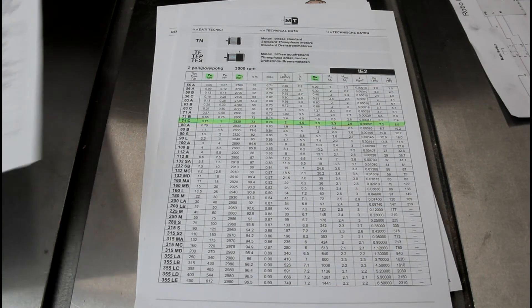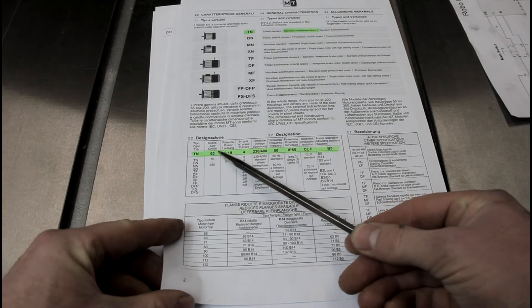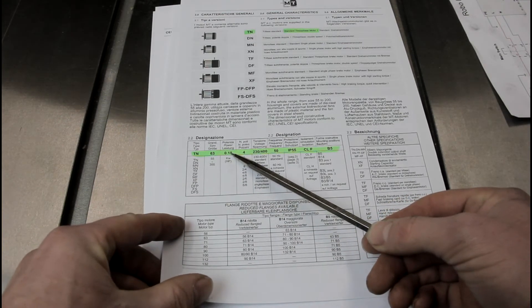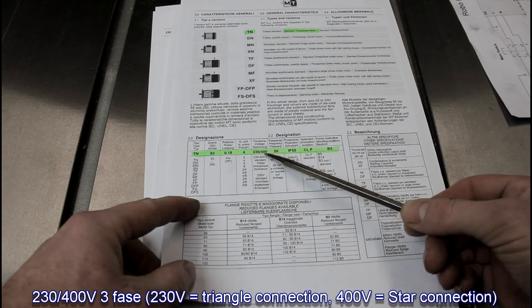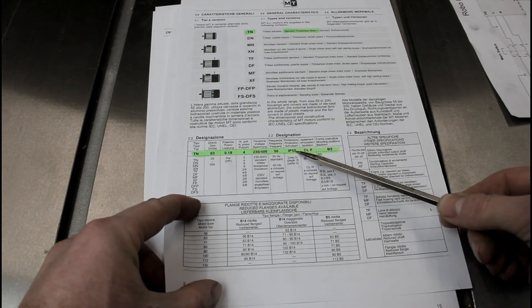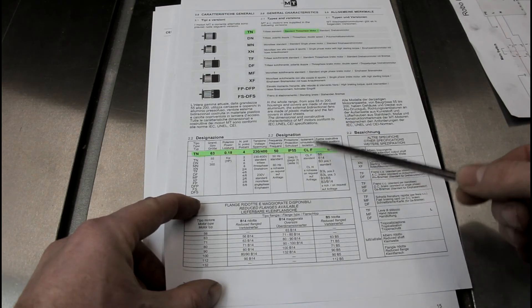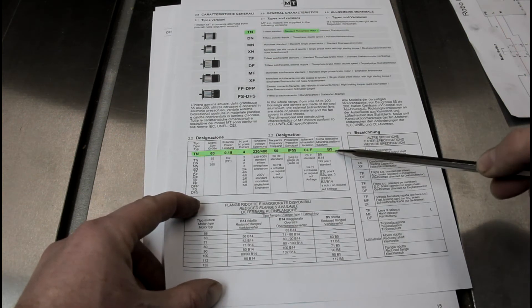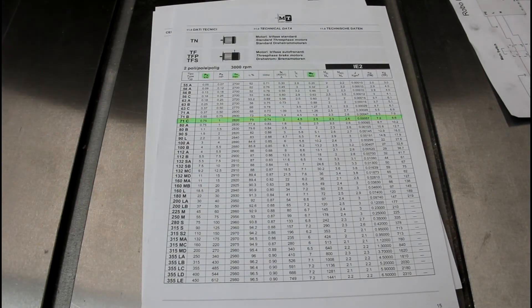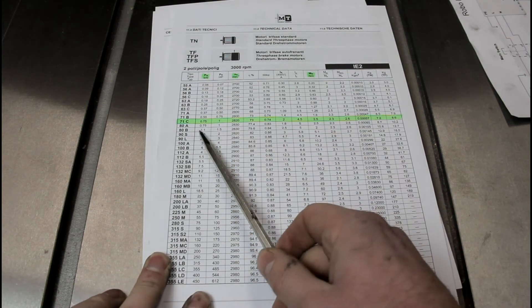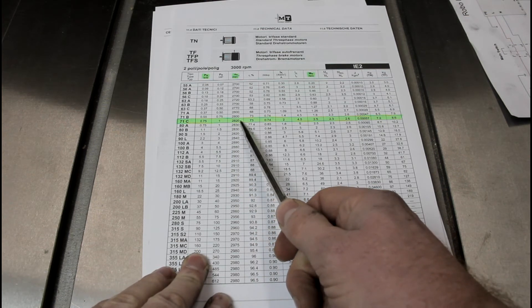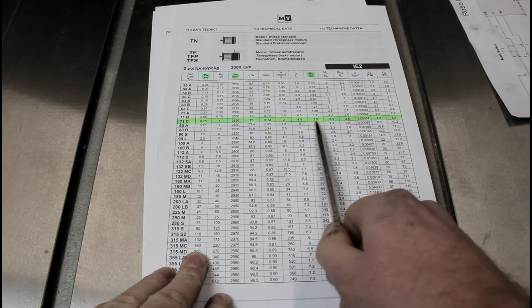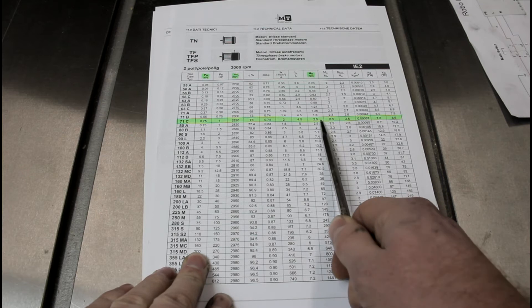So before we go even further, we can already order our motor. It's a TN type, it's a 71 size, it's a 750 watts, so a 0.75 kilowatt motor. It has 2 poles, 230 volts, 50 hertz. The standard protection rate for water is IP55, which is great for me. A standard class F insulation is great for me, and the B3 type mount. So let's have a look at this motor. It's the 71C, 2 pole motor, 750 watts, it's 1 horsepower, it has 2820 rpms. And most importantly, we have 2.5 newton meters of torque, nominal torque.